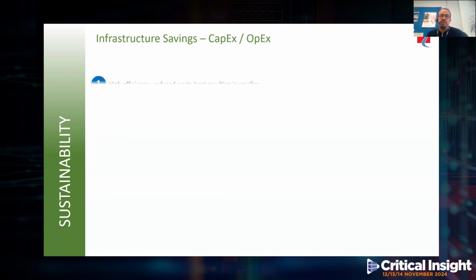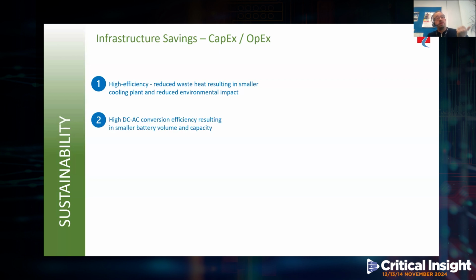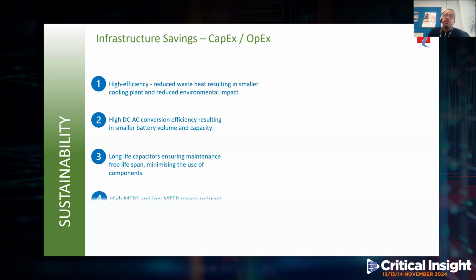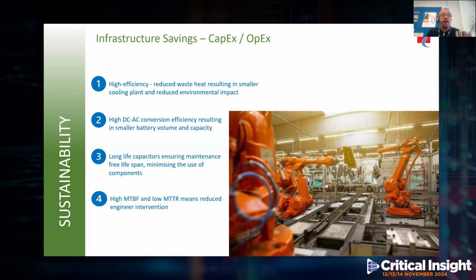Now, there are further benefits. The high efficiency means reduced wasted heat, resulting in smaller cooling plant on site. The high DC to AC conversion efficiency can result in much smaller batteries in terms of volume and capacity. The systems operate with long life capacitors, ensuring a maintenance-free lifespan. Now, a traditional UPS will have its capacitors changed around years 5 to 7, but in this case, they will operate for a full 15 years of operation without being changed. The systems can provide a high mean time between failure, a low mean time to repair, and are obviously very easy to use, which means reduced engineer intervention. And basically, all of these key points result in significant CapEx and OpEx savings, but most importantly, obviously, lower the environmental impacts.